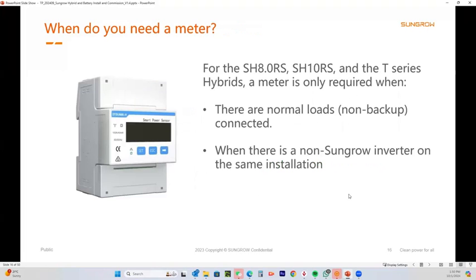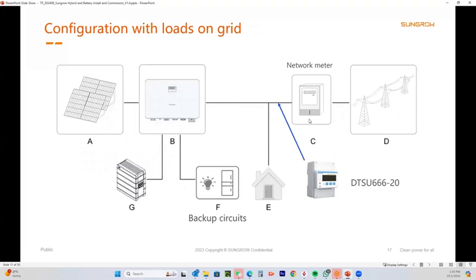That's not a problem. So the only time you actually do need to connect a meter, the DTSU666-20, there's two cases, and I'm going to show you these in a moment. Configuration with loads on grid. This is where you only have the emergency circuits on the backup and you've got the major house loads just on here like this. In this case, you will need to install the meter because it's the only method we have of measuring consumption to the loads. So if you have normal loads, you will need the meter.